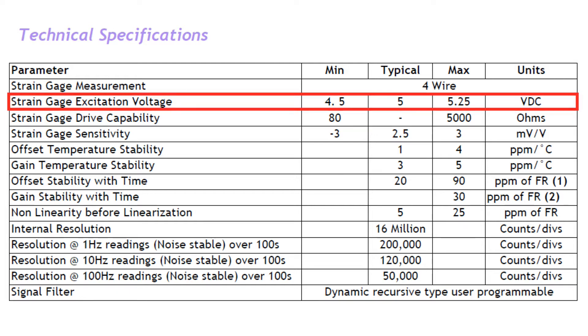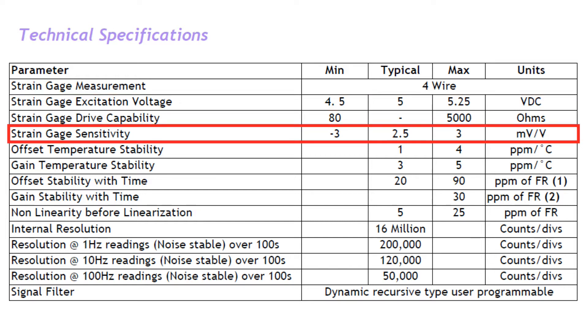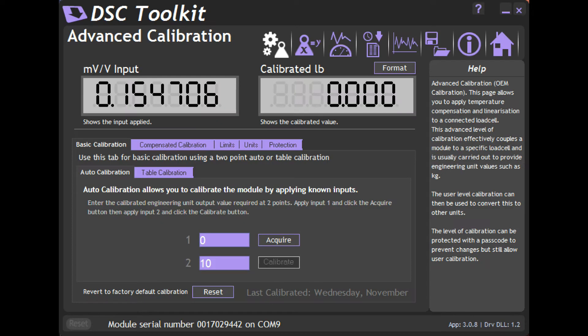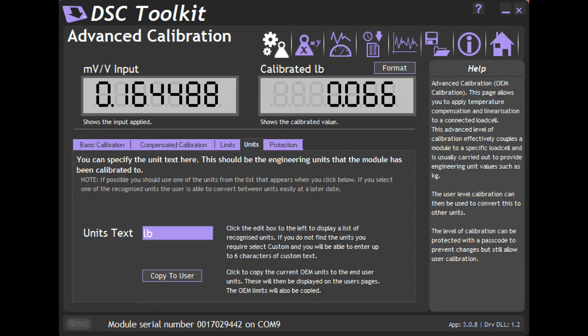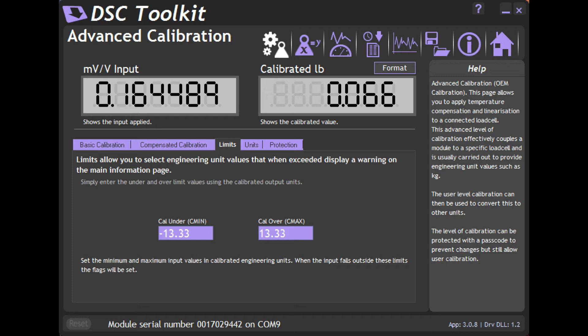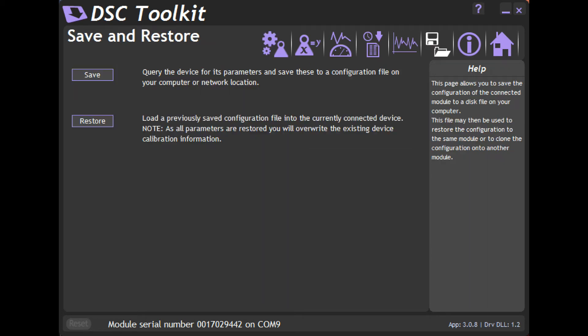The DSC-USB provides 5 volts excitation and is factory adjustable sensitivity for use with virtually any strain gauge load cell. It is configured with its DSC toolkit software which allows for calibration, unit conversions, real-time graphs, overload settings, weight value format, and the ability to save and load DSC files for use with multiple load cells.